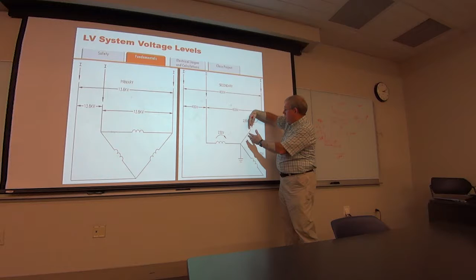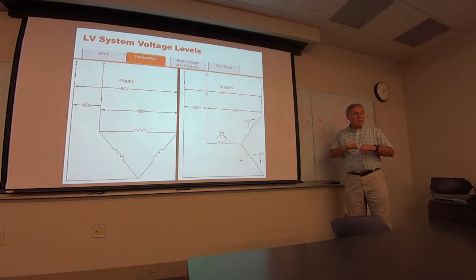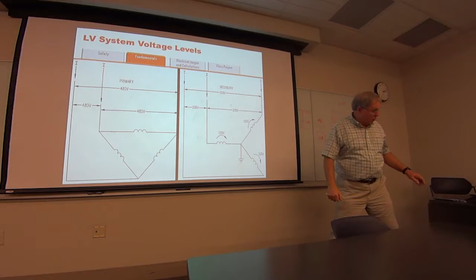And if you have a 208 volt system, or if you have 230 volt rack equipment and you've got 208 volt transformers, raise the taps on the transformers as high as you can get them. Because here's the point where your computer or whatever will drop out. Here's 208 volts. Here's 230 volts. You give yourself more headroom if you're having problems with power quality events. Of course, we tried that with some and it didn't work too good, but in theory, it's supposed to work.